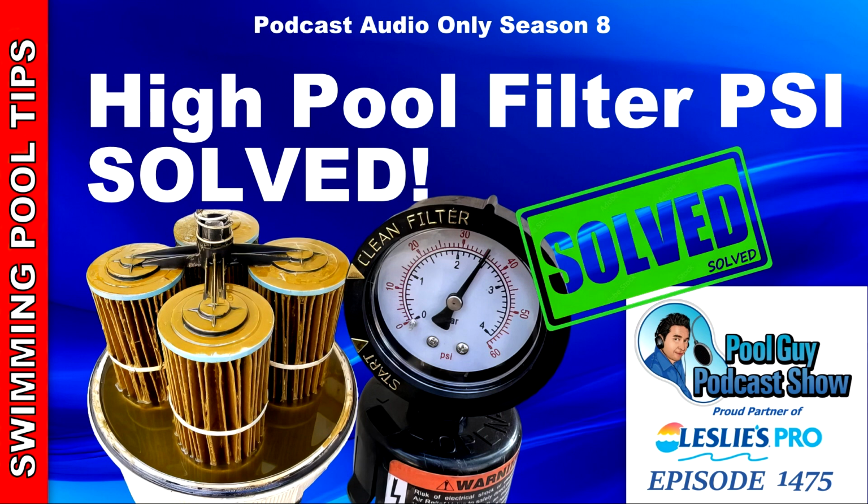But usually, if the bands are really broken and the pleats are really wide on those, I'll change them out. But they seem to last a very long time with really no issues and no tears or problems. So I would say the quad D filters are very long lasting. I would probably go 5 or 6 years with those. But the regular grid type, I would just go ahead and change those grids out every 3 years without even hesitating, because then you're going to have fresh filter grids or elements and everything will be fine.